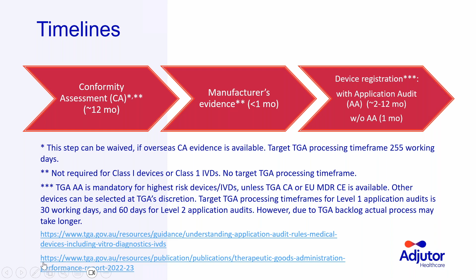Now, what if your product has overseas approval? As mentioned in the previous slides, all devices require conformity assessment evidence except the lowest risk class 1. The good news is that you can leverage the CE mark or CE certificate you may have in lieu of a TGA conformity assessment. This can save you a significant amount of time and money. Some common examples are listed on this slide.